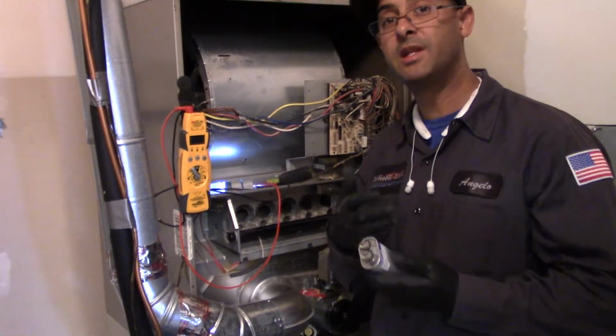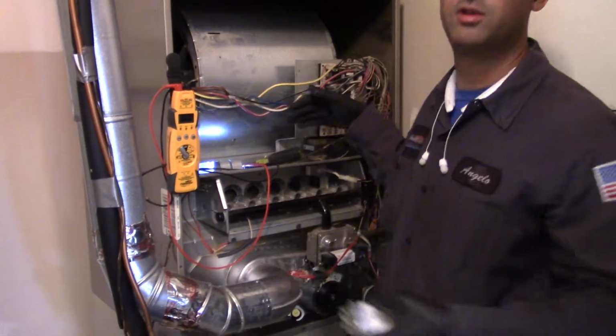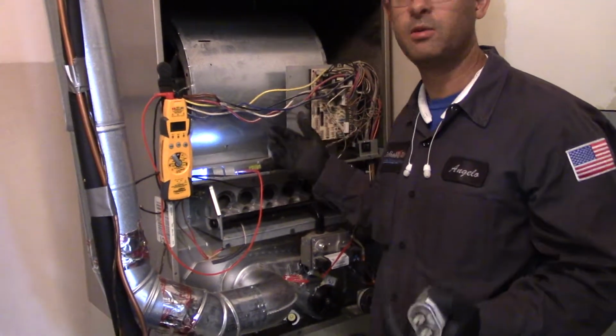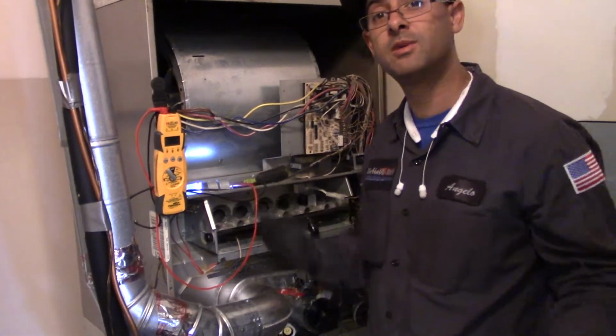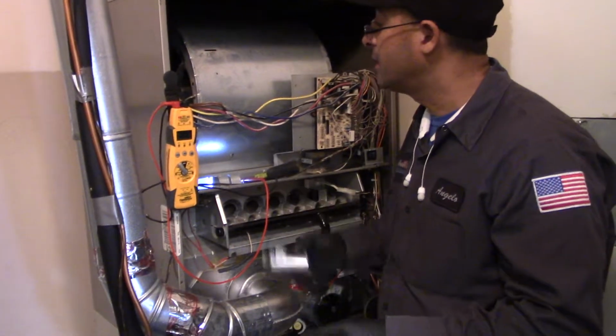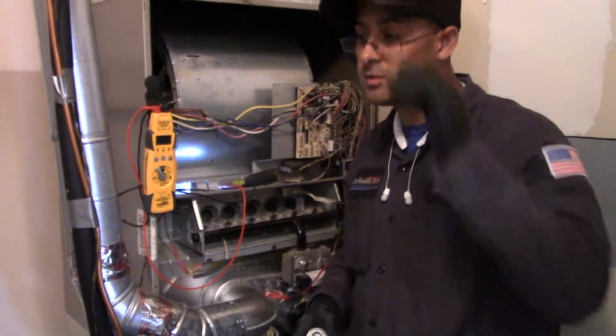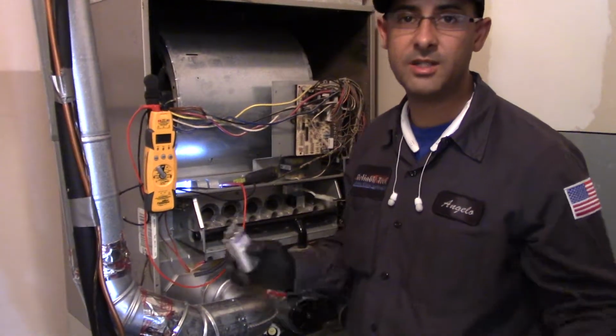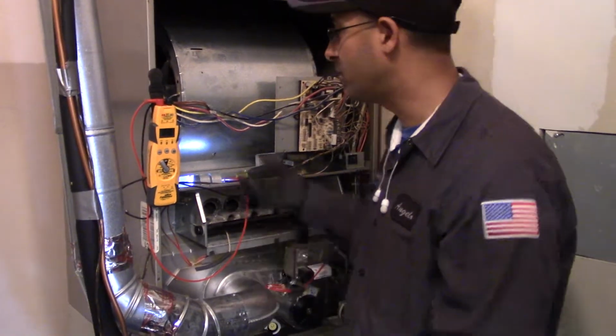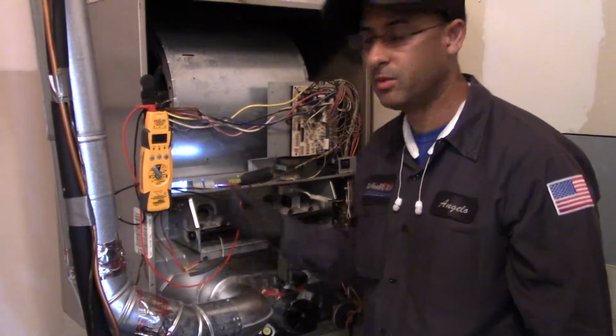Okay? Because it might be that the capacitor caused the motor to run hot, overamp, and now the motor's bad, so now we've got to replace the motor and the capacitor. Now, anytime you're replacing the motor, it's just a rule of thumb to replace the capacitor as well. So you don't want to put a new motor in there and it craps out in 6 months. We want it to last a long time.